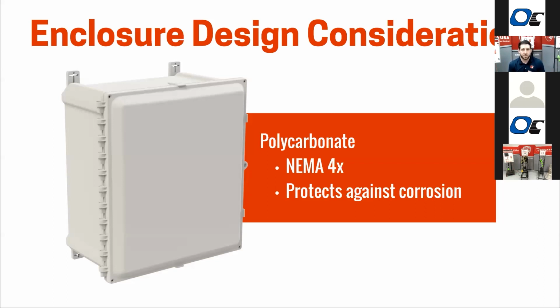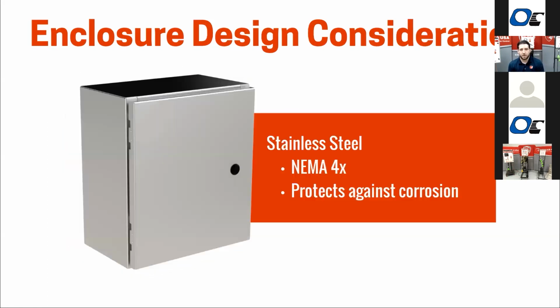We typically recommend that junction boxes, if you have to have one between the pit and the control panel, be outside of the pit itself, outside of the wet well. But if it has to be in the wet well for whatever reason, you can use this enclosure with some cord grips and a terminal strip, and it gives you the closest to a waterproof connection that you're going to get inside the wet well. The other option: we are limited on size with the poly enclosure. So anything larger than, I think, an 18-16 enclosure, we're going to move up to stainless steel. The difference between NEMA 4 and NEMA 4X is that corrosion protection, so stainless is a great option for that. And really, it's not much of a premium to go to that.